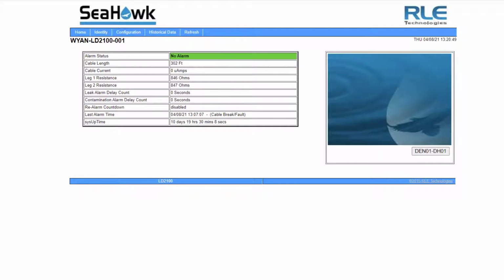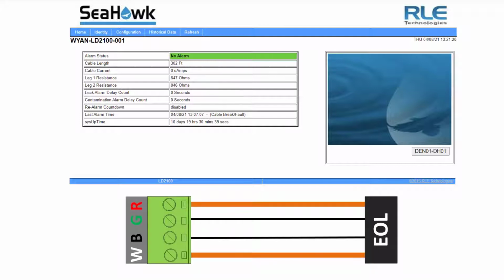I'm going to go over a basic overview of the cable operation on the RLE distance read controllers, and then how to do a calibration based on what we have tied to that system. So starting off, the RLE distance read controllers, whether you have an old LD2500 model or one of the newer models being offered today, are considered to be supervised type systems. The supervision comes in place because the controller is constantly not only looking for a leak, but it's looking for the integrity of that leak detection cable being hooked up to it.